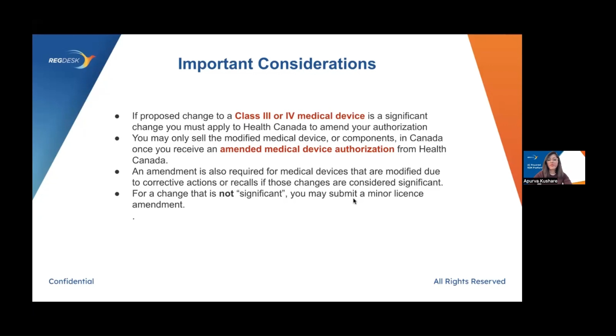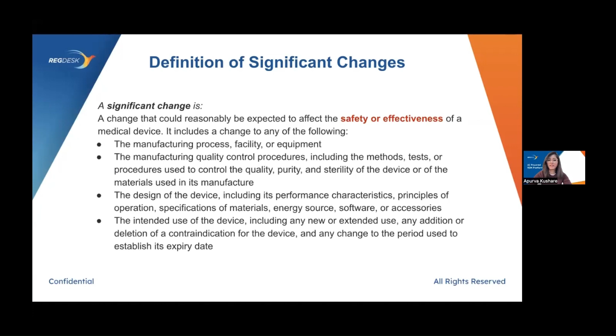So a significant change is a change that could reasonably be expected to affect the safety or effectiveness of the medical device. So this includes any changes to the manufacturing process, facility, or equipment. It can be manufacturing quality control procedures, which include the methods, tests, and procedures used to control the quality, purity, and sterility of the device or of the materials used in its manufacturing. Then the design of the device, which is very important, including its performance characteristics, principles of operation, specifications of materials, energy source, software, or accessories. Also, any changes to the intended use of the device, including any new or extended use, any addition or deletion of a contraindication for a device, and any change to the period used to establish its expiry date.